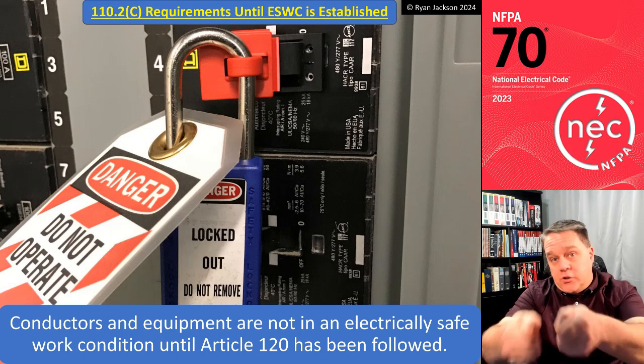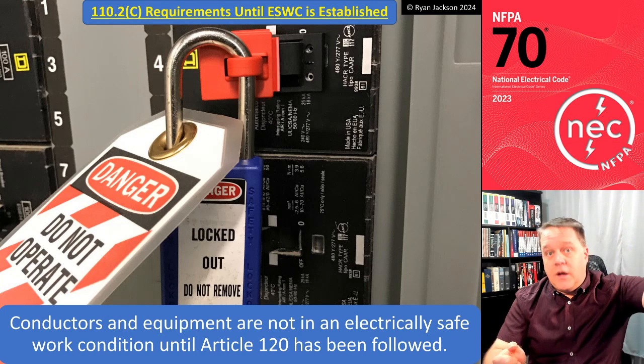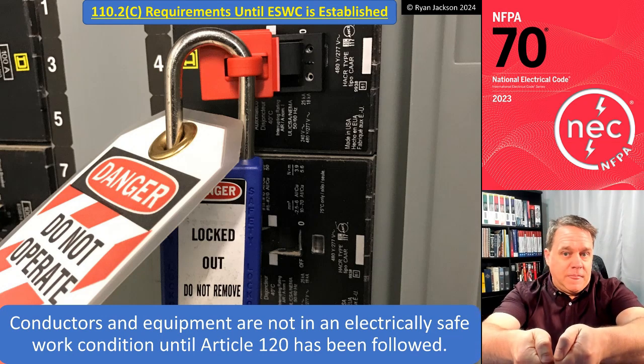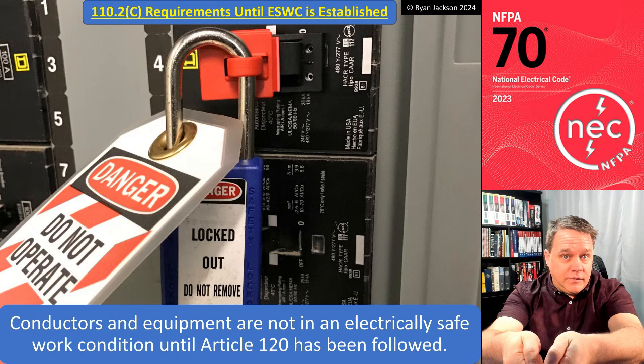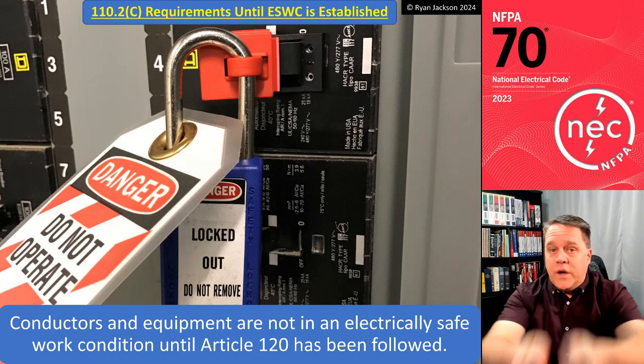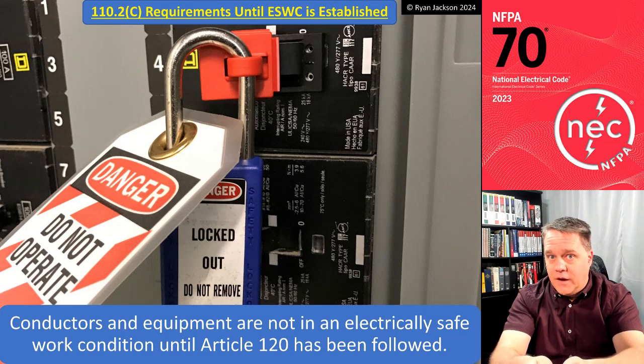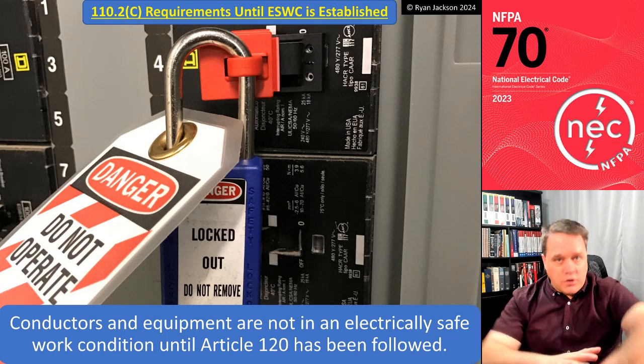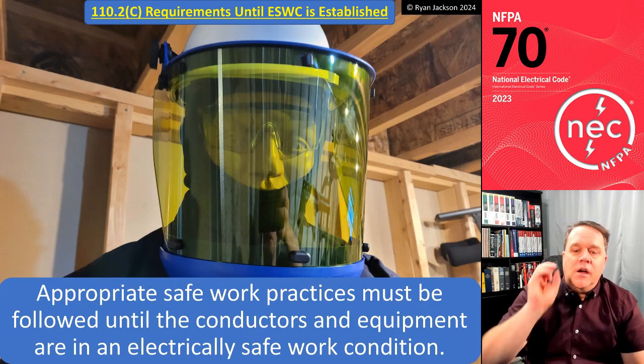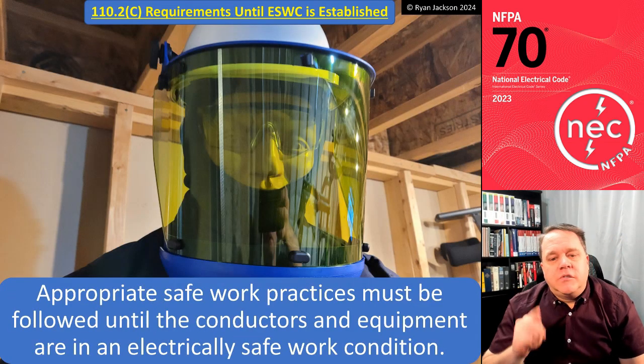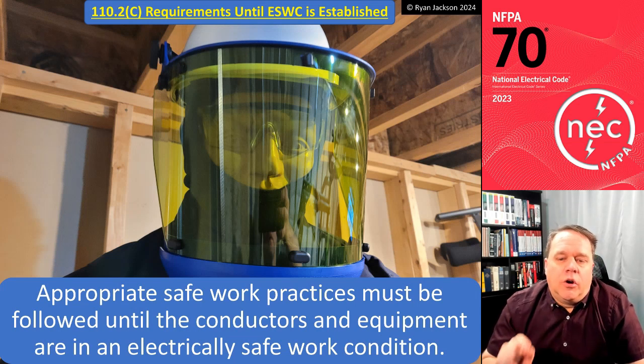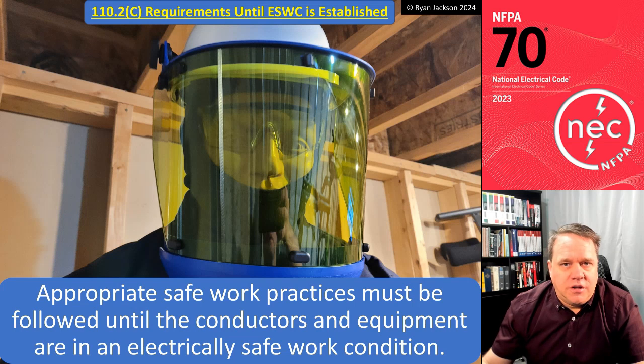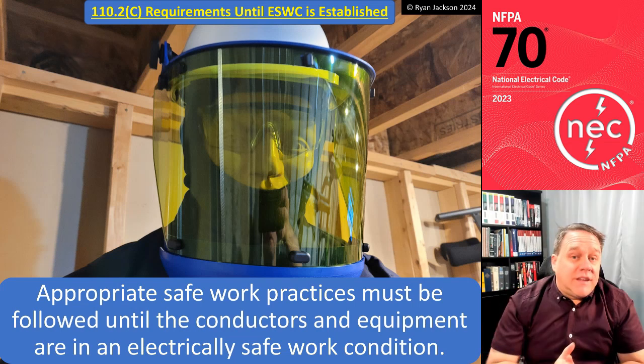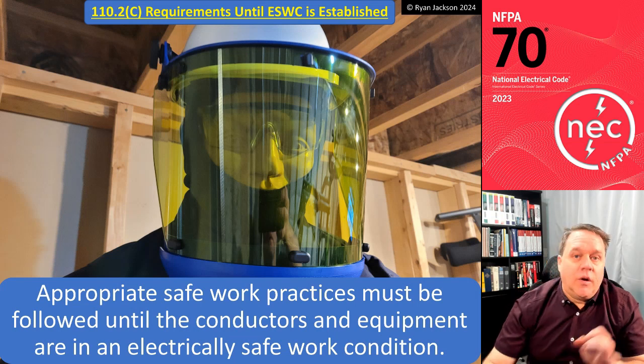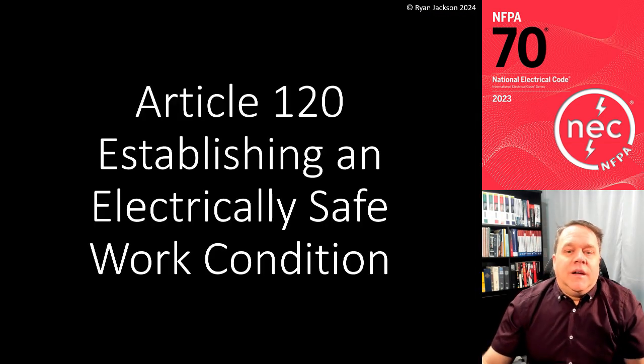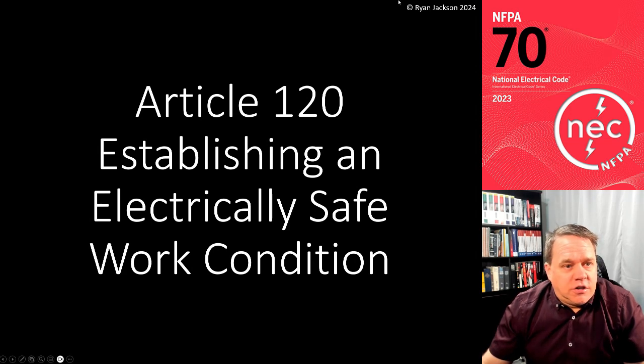So when I'm measuring for the absence of voltage, right, I've shut it off, I've locked it out, I've got in there with my tester. Even if it shows that it's off, until you've verified it, we've got to pretend that it's still on. All right, so until you're done with Article 120, you're not in an electrically safe work condition, which means appropriate safe work practices must be followed until the conductors and equipment are in an electrically safe work condition. All right, so that takes care of Article 110. Let's go ahead and jump into Article 120, which is establishing an electrically safe work condition.